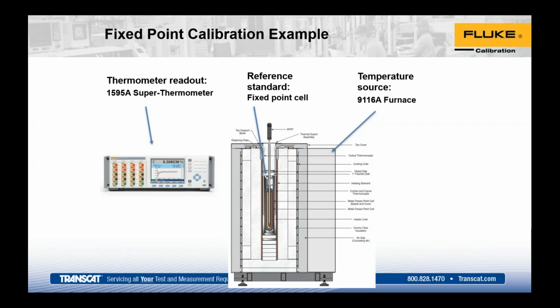But for fixed point calibration work, there's more than just one piece that goes into it. You can't just have a fixed point cell and you're good to go. Most of them require a maintenance apparatus. This can be a furnace or a bath. For some of the lower temperature work, baths are used, like for the triple point of mercury. You've got to cool it down to about -38, -40 to make it happen. And then once you achieve your plateau, you've got to have a way of transfer. So you've got your SPRT and then a really good thermometer or bridge to take that resistance reading.